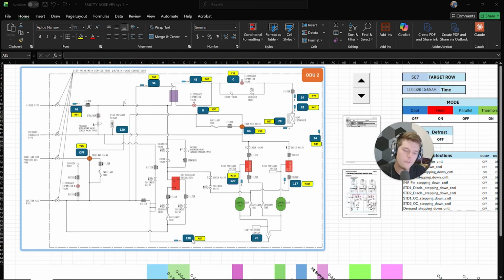And so for those who are not familiar with the system and the refrigerant flow of these systems, this is how the macros are used. It's a learning tool. Do not use it as a crutch. Do not think that you can't look at service checker data unless you put it into the macro. The macro is designed to help you learn the flow of refrigerant and where the sensors are and their designations, right? To find the clogged filter strainer between here and here, or maybe it's this one here, or find a leak past this valve. This is what it's designed for.